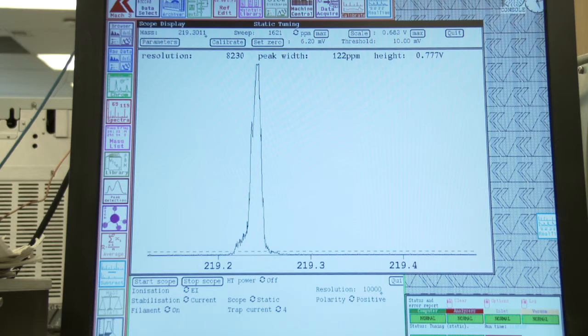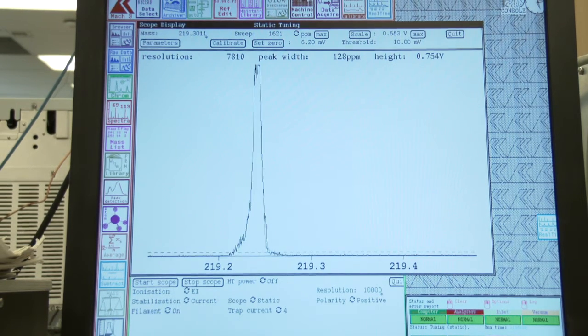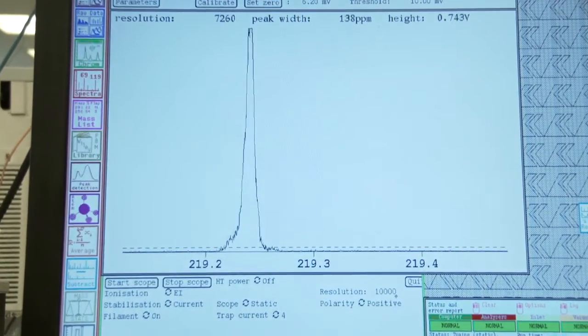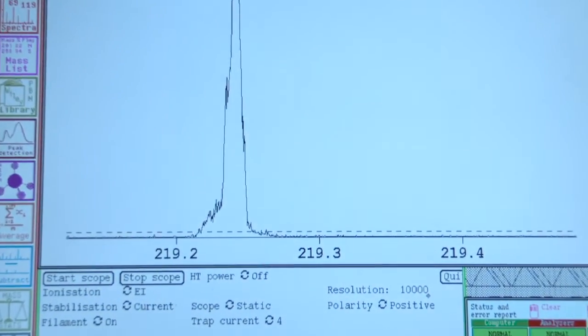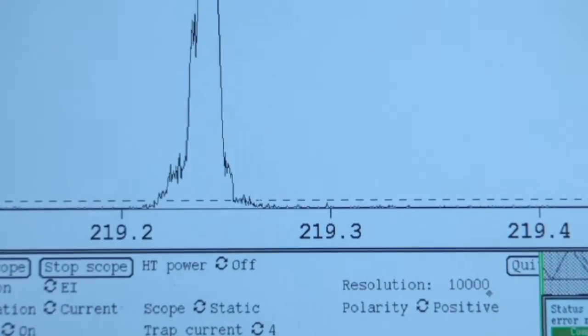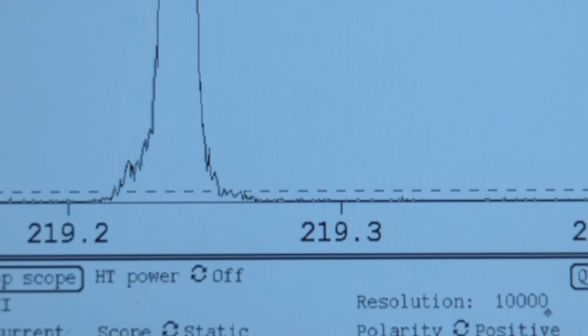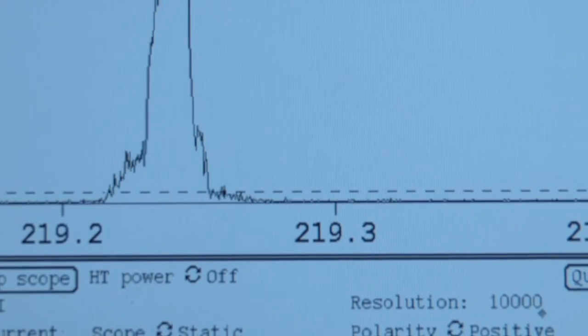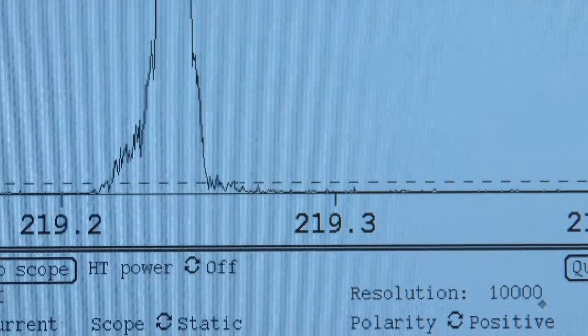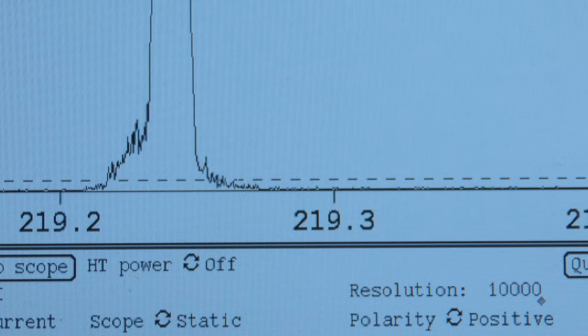This scan shows a small mass range around 219 Dalton. This PFK peak is used to optimize the voltages within the source and to physically narrow the slits in the instrument to produce the narrowest peak possible. And you can see that this peak is less than 0.05 Dalton wide, producing a resolution near 10,000. We try to achieve this resolution every time we run the experiment. This then allows us to use the accurate mass data acquired when running a sample to verify the molecular formula. And here's how that is done.